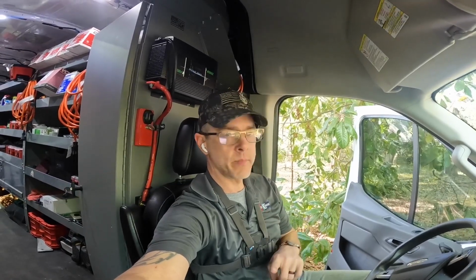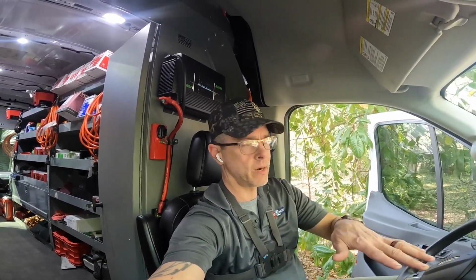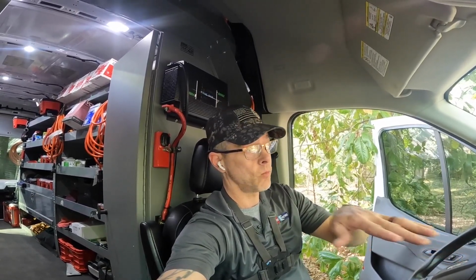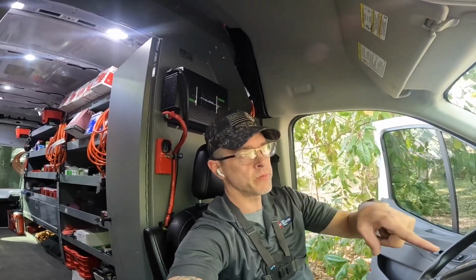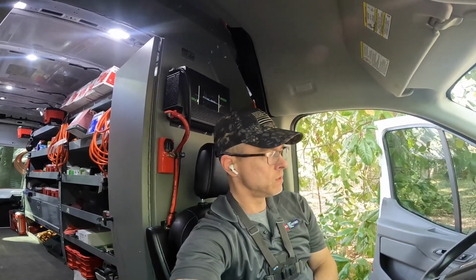All right, that might be a Maytag, but that nameplate looked every bit like a Nordyne. Either way, I've got to do a little bit of research and make sure I'm supposed to be getting a 24-volt signal down on that other board. I'm pretty sure that's what it is because I have all my thermostat wires there. Wire for wire, that looks like thermostat wires instead of a communication wire. So I think I'm supposed to be getting 24 volts down on that board to tell it to bring on that variable speed motor. But I'm going to read up on it anyway.